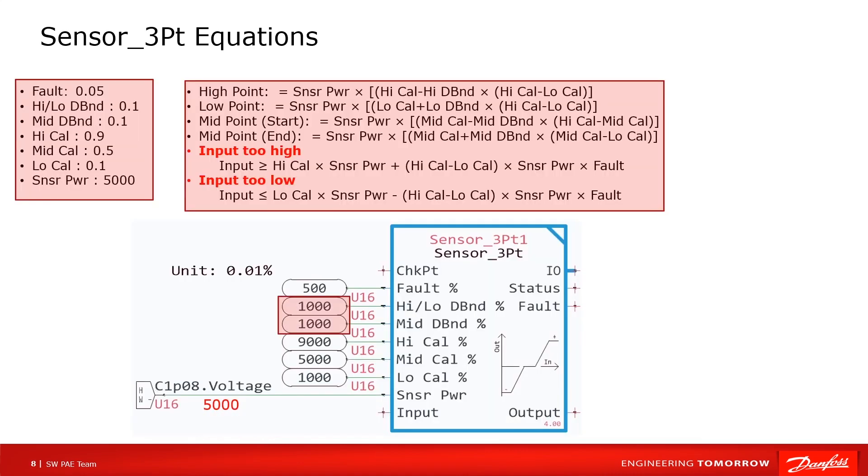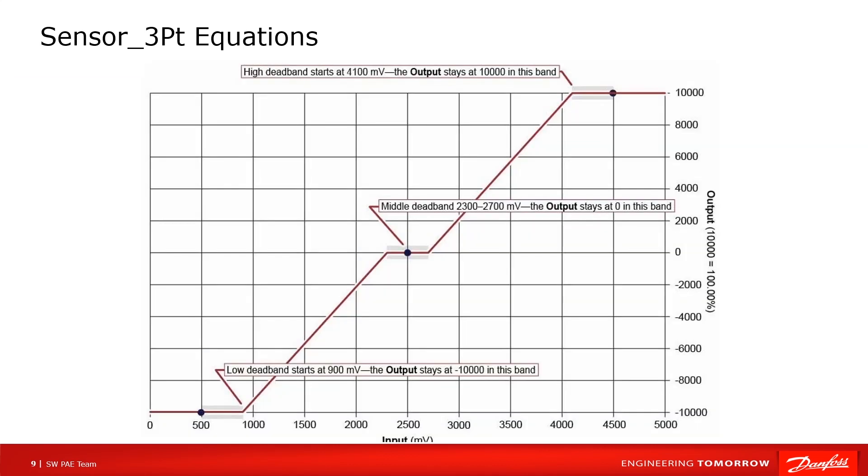Now we set the dead band to 1000 and take it into formulas again. We can get the calculation result. High point is 4100, middle area ranges from 2300 to 2700, low point is 900. Let's check the trace.